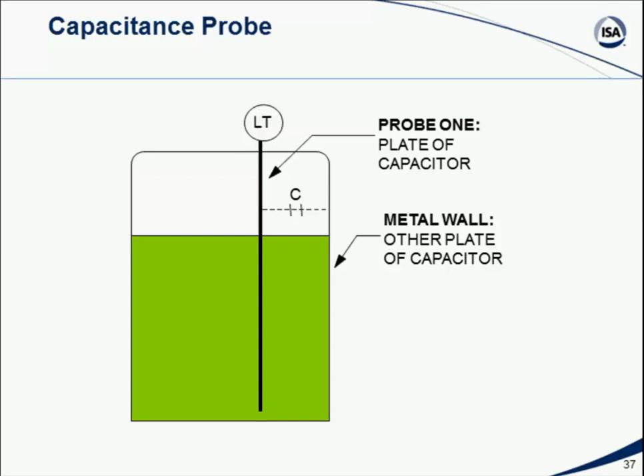And if I make an electrical measurement across them, that capacitance is something I can measure. Well, as the fluid level in a tank goes up and down, especially in this case where we're talking about a non-conductive fluid, it actually changes the measurable capacitance of this two-conductor capacitor we've created. So by measuring the capacitance between the probe metal and the wall metal of the tank, I can make an inferential calculation of the level in the tank. And a capacitive probe level measurement device is a very typical thing we use these days.